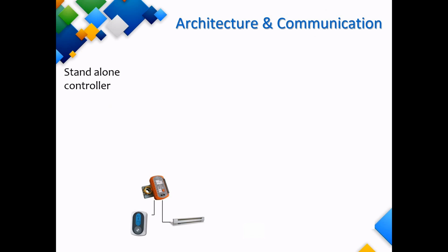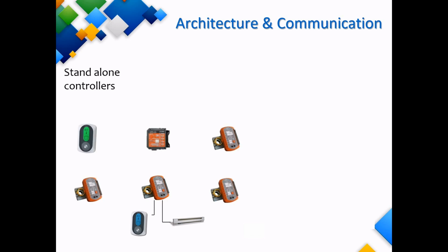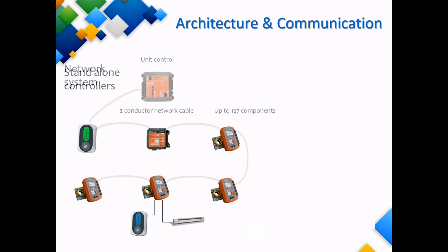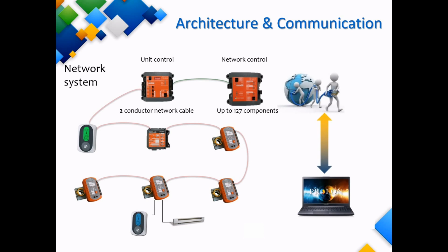Okay, so that wraps it up for the controller overview. In terms of architecture, a project can start off with simple standalone controllers being installed one at a time. If the customer would like a networked system, at this point we can simply connect all the controllers together in a daisy chain using a 2-conductor cable. We can have up to 127 controllers on a single network. When we add the network controller, now we can access our system remotely via the internet.